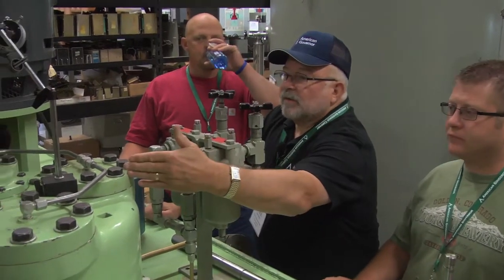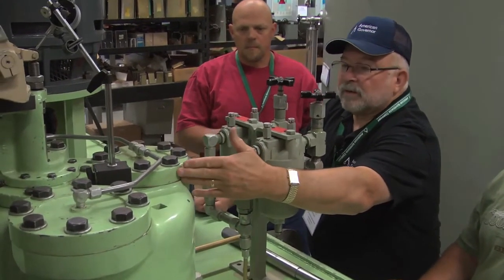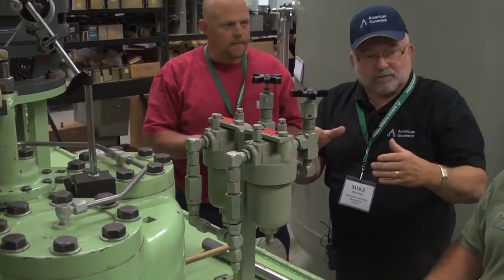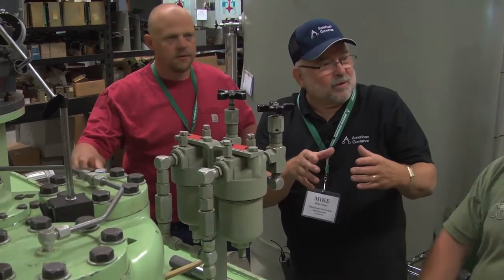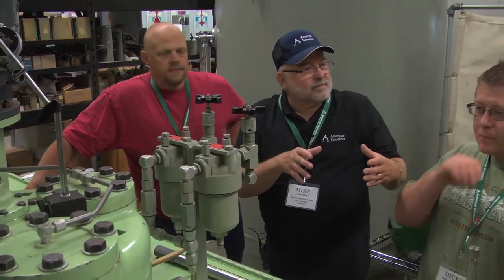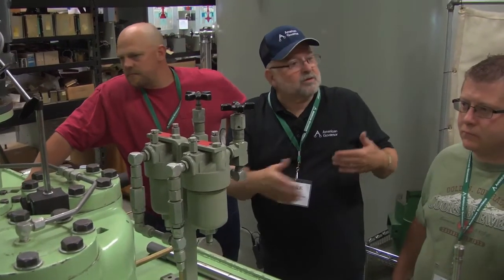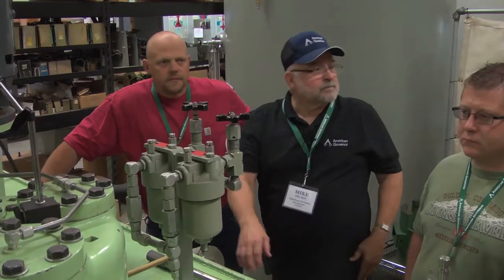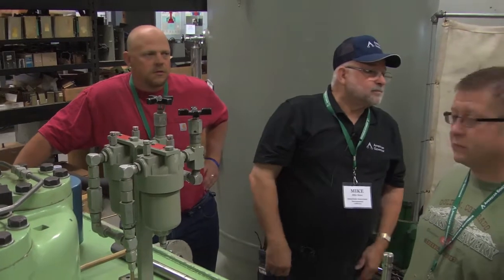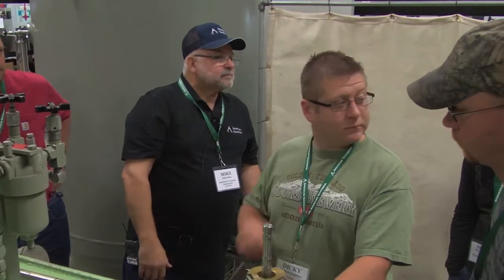This is a new duplex setup here. You know, these distributing valves are the same as a Woodward. A lot of the Pelton distributing valves, relay valves, are pretty small. Some of them are only as big as an aux valve. Depending on the type of unit and how much stroke it's got, it may not need much. What's the stroke, and the size of the servos? Oh yeah, you know, that's the difference. Our servos are pistons probably this big. Oh yeah, see, that takes a lot of oil moving, so it's got to have a big valve.